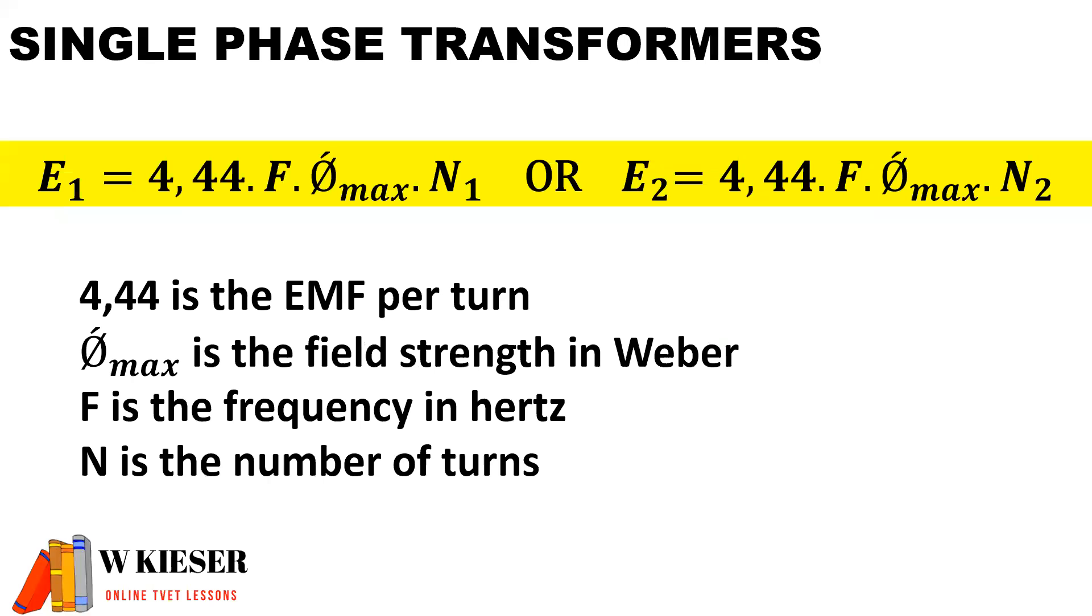In the equations we're going to be using for our stacking factor and calculations for single-phase transformers, you'll notice that the EMF on the primary side is equal to 4.44 multiplied by the frequency of 50 hertz, normally 50 hertz but it could change, and then we have the maximum flux per pole in Weber, and then we have the number of primary turns.